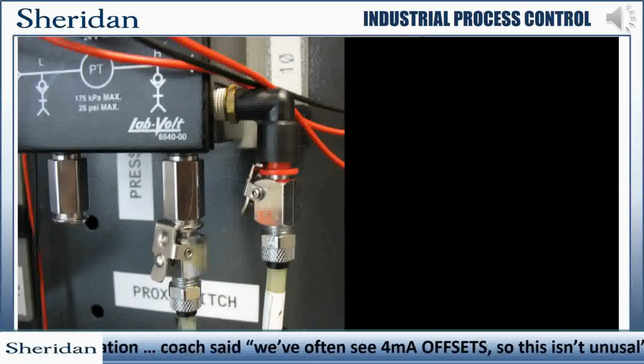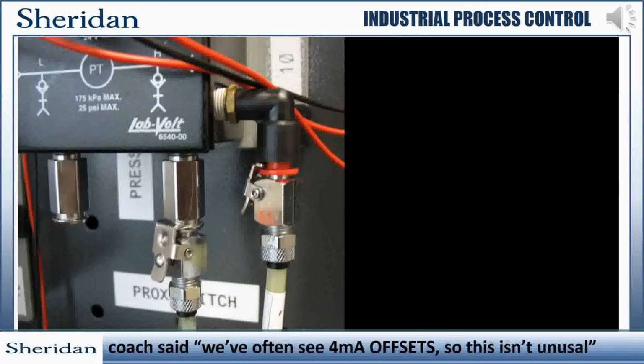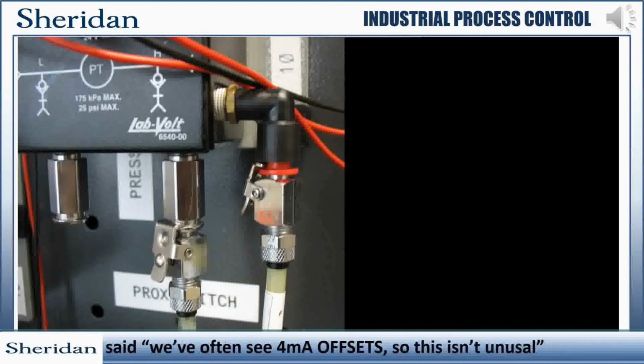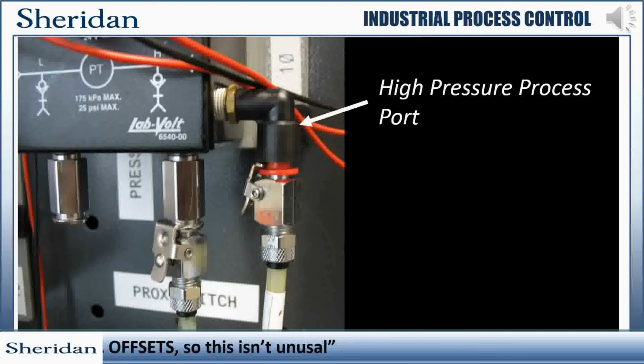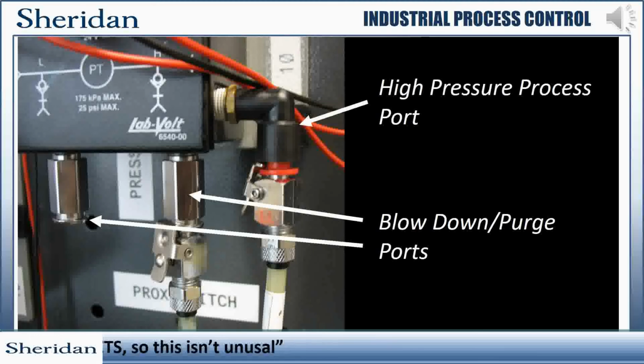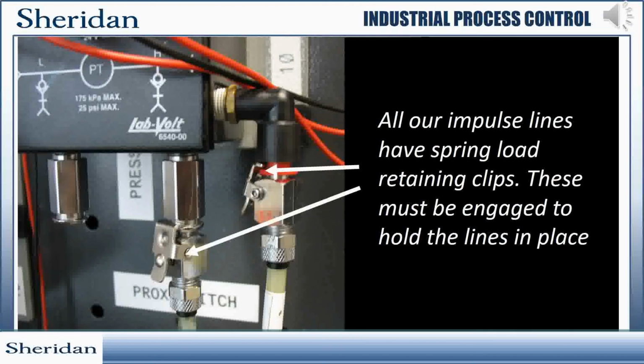The transmitter will be performing as a differential pressure transmitter. That is, its signal will indicate the difference in pressure between its process ports. On the transmitter itself, there are 4 quick connection ports. The ports located on the side are the process ports, while the bottom ports are for blowing down or purging. The right-hand process port is for the expected high-pressure process connection, while the left-hand process port is for the expected low-pressure process connection.